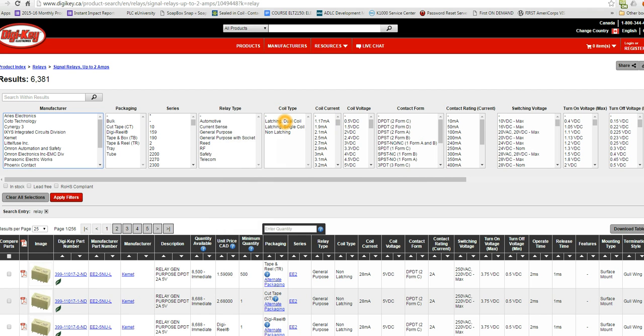It could be a latching relay or non-latching. Most of our relays we're going to be looking at are non-latching. Latching relays, when you turn them on, they stay on and you have to apply another voltage to another coil to turn them off. Non-latching relays, when you apply power to the coils, they'll turn on, but as soon as you relieve that power, the relay relaxes.